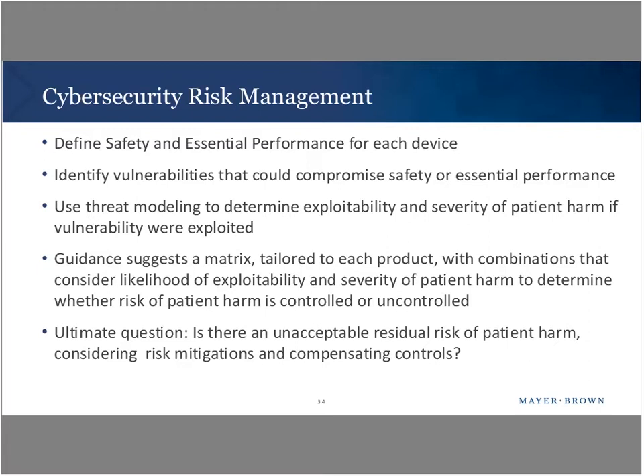And those risk mitigations and compensating controls are things that are either built into the device or deployed through a patch to help mitigate and control the risks. Going back to the combinations of the likelihood of exploitability and the severity of patient harm, FDA wants you to look at how much likelihood there is and what the severity of the patient harm would be. And if you have, for example, a high patient harm but a very, very low likelihood that it would ever happen, then it might be a controlled risk. On the flip side, if the patient harm was low, but the exploitability was very, very likely, you might have more of an uncontrolled risk.